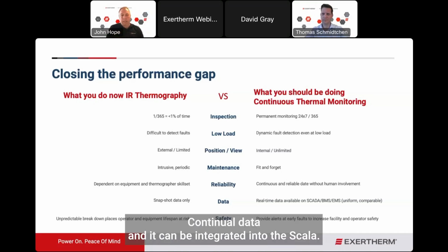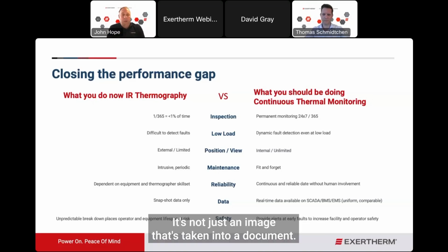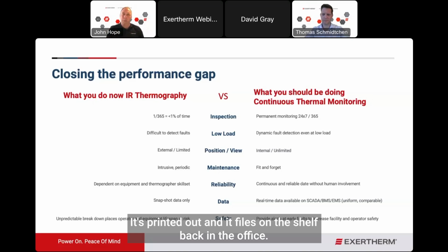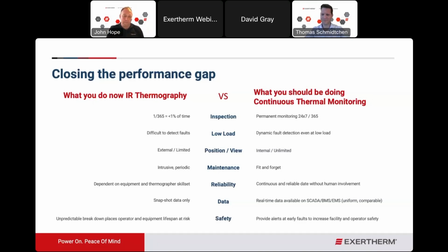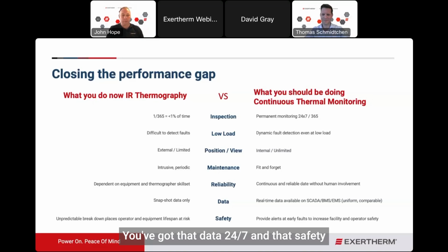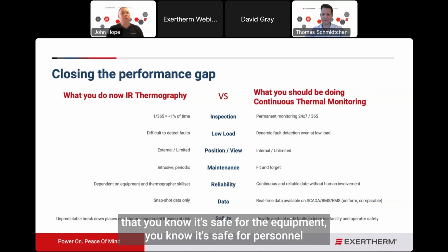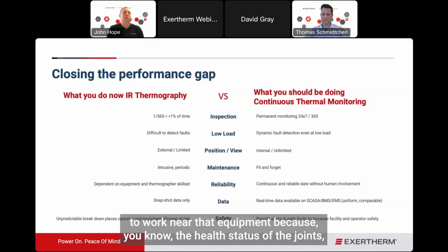It's continual data, and it can be integrated into the SCADA. It's not just an image that's taken into a document, printed out, and filed on the shelf back in the office. You've got that data 24/7. And that safety is giving you those alerts that you know it's safe for the equipment. You know it's safe for personnel to work near that equipment because you know the health status of the joints.